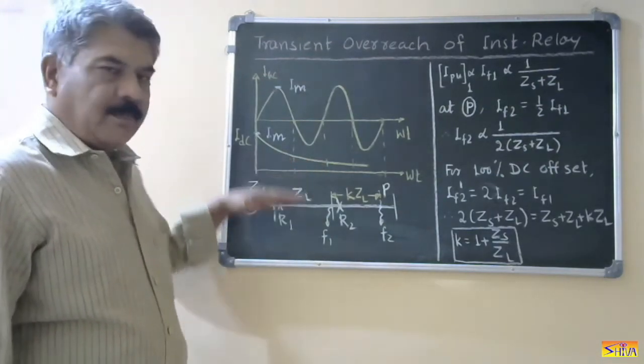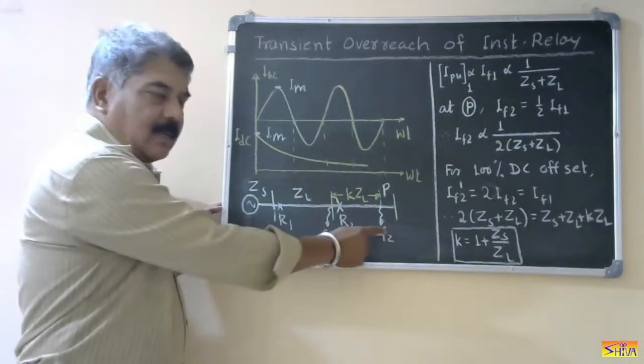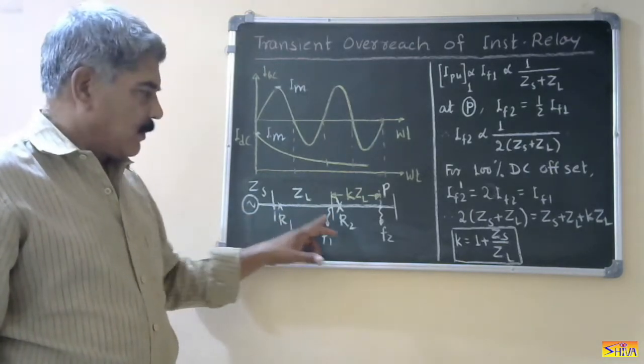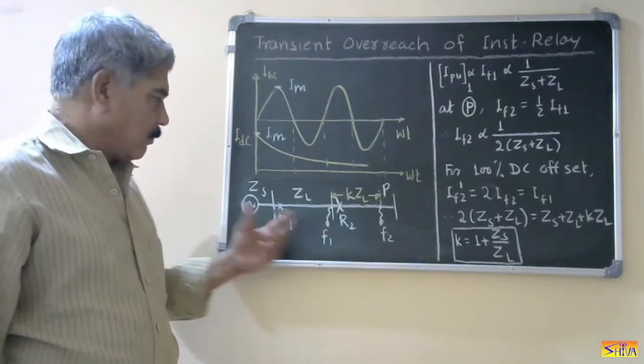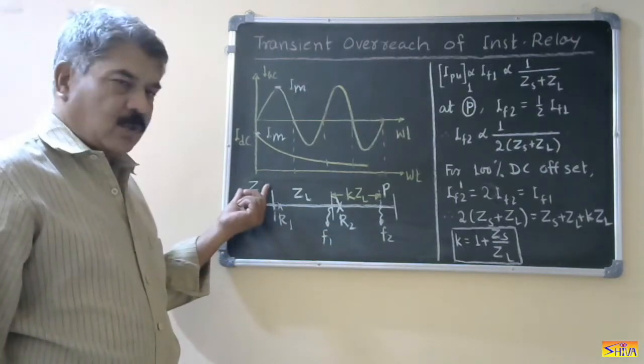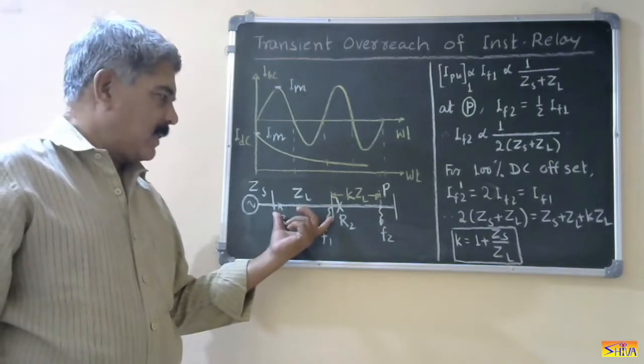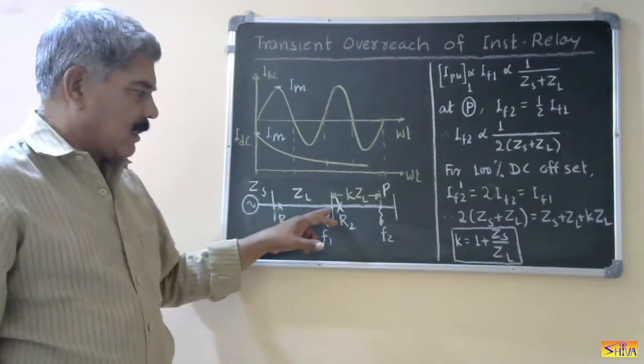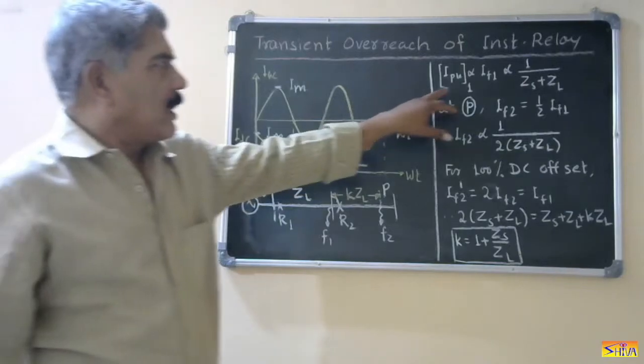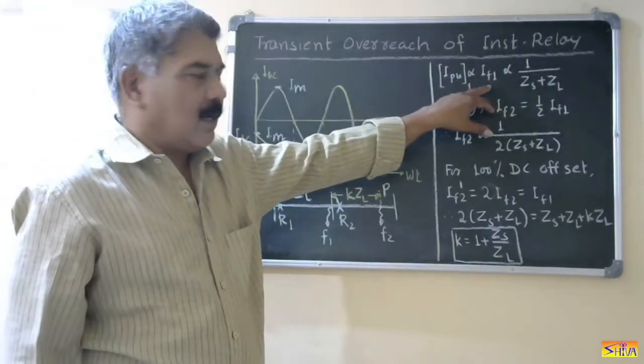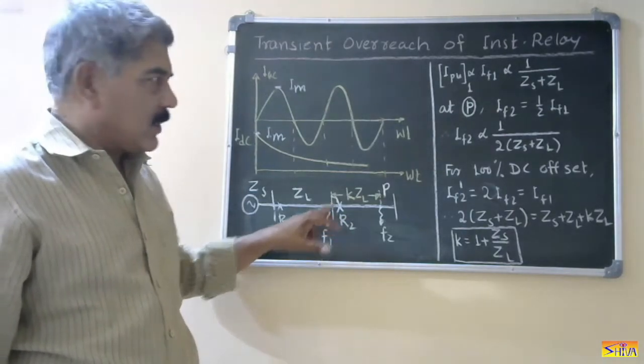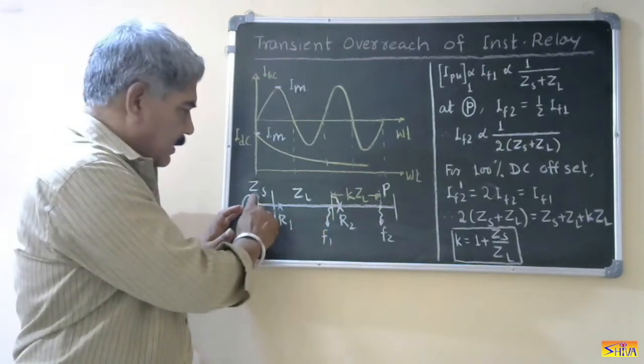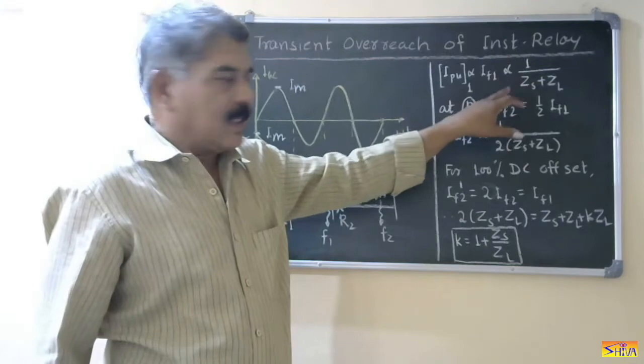Now let us come to the relay. For this simple radial system we have two sections from the source. For the first section we are using relay R1, and for the second section relay R2. ZS is source impedance and ZL is impedance of the line. We set relay R1 by considering the fault at the remote location F1, so the pickup of relay R1 will be proportional to 1 upon ZS plus ZL.